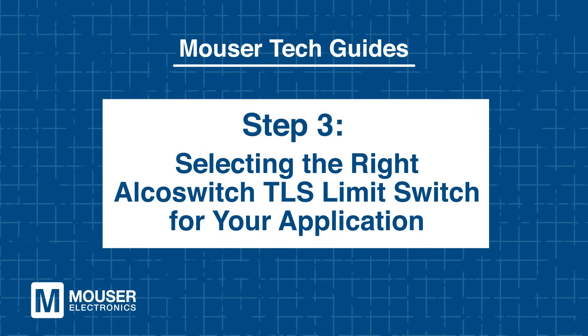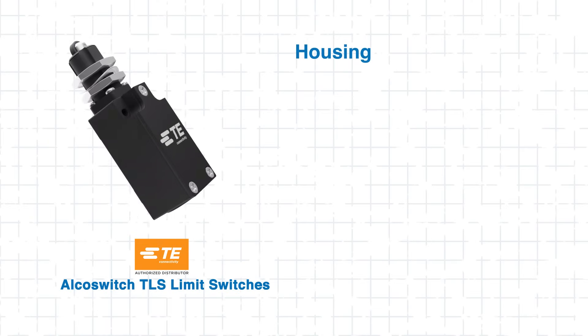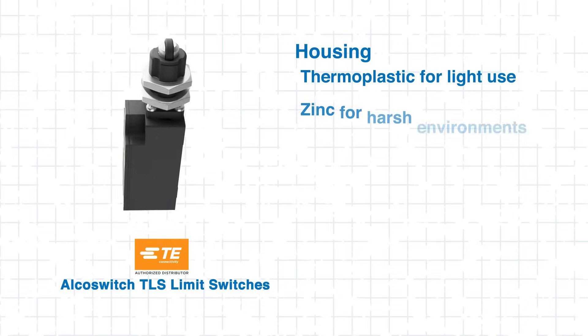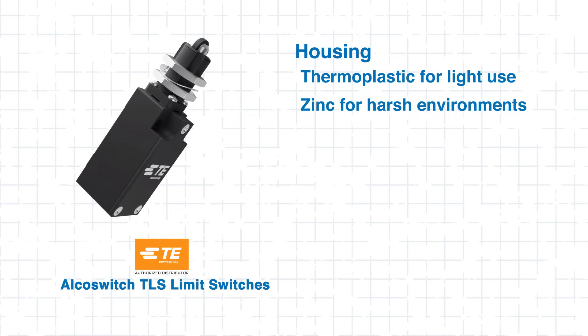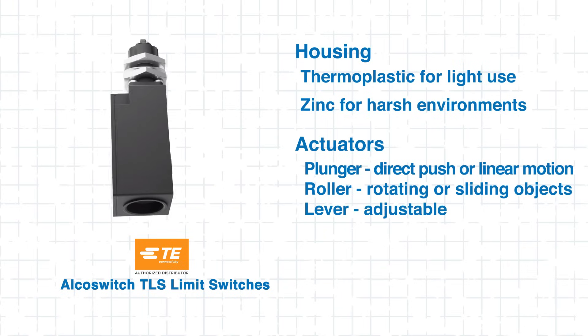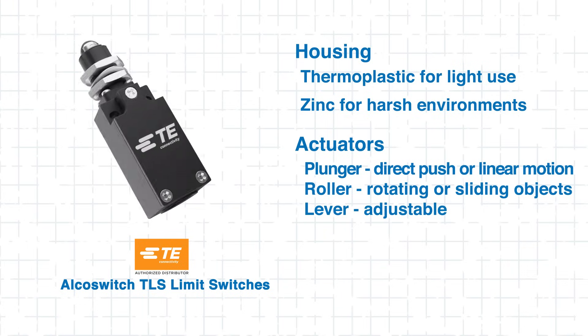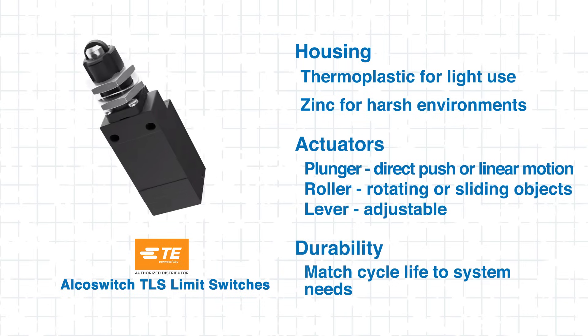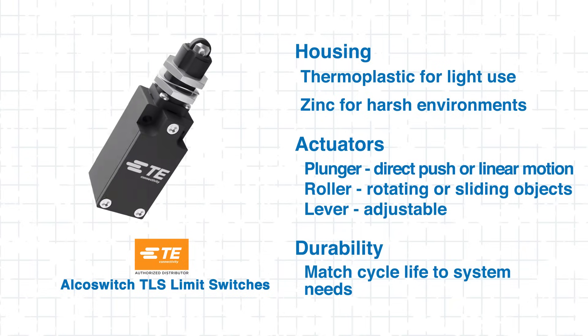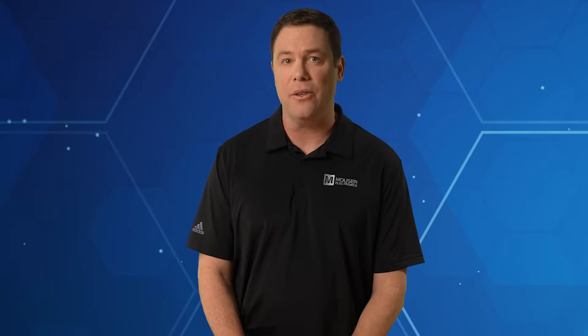Step 3: Selecting the Right AlcoSwitch TLS Limit Switch for Your Application. Choosing the right TLS Limit Switch is essential for maximizing system performance. Start by considering the housing material — thermoplastic is ideal for lighter-duty applications, while zinc provides added durability for more rugged environments. The actuator type should be matched to your application: plunger for direct push or linear motion, roller for rotating or sliding objects, and lever for adjustable motion. You'll also need to ensure the switch's cycle life meets or exceeds the expected number of actuation cycles in your system.